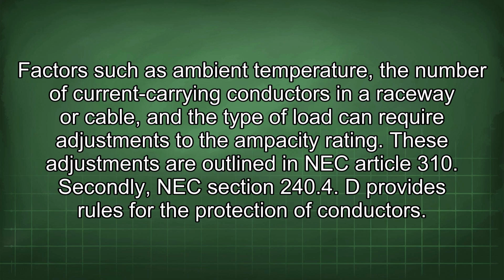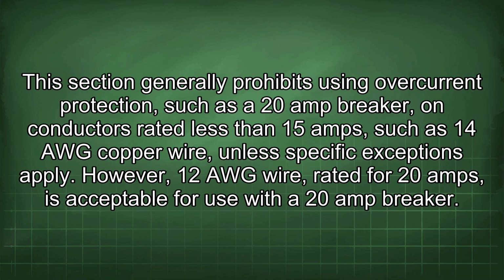Secondly, NEC Section 240.4(D) provides rules for the protection of conductors. This section generally prohibits using overcurrent protection, such as a 20 amp breaker, on conductors rated less than 15 amps, such as 14 AWG copper wire, unless specific exceptions apply. However, 12 AWG wire, rated for 20 amps, is acceptable for use with a 20 amp breaker.